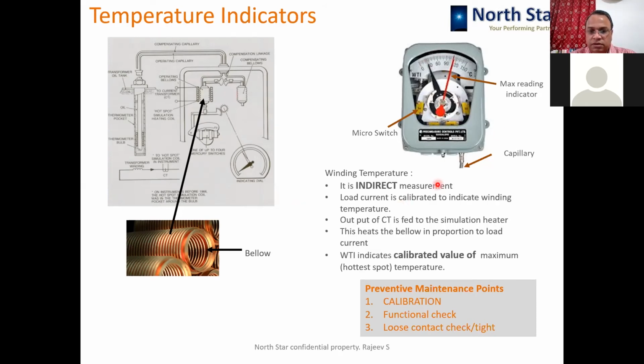So it is critical that the calibration of the WTI is done. The WTI coming from the factory is not set to indicate the exact hotspot, because the exact gradient can only be known by performing the temperature rise test on the transformer. So if you want to get the true hotspot reading of the WTI, you can do it by measuring the gradient by conducting the temperature rise test and then setting the resistor of the WTI accordingly. Then only it will show you the hotspot temperature. Otherwise, it will show you something in between average and hotspot temperature. Okay, so that is an important point.